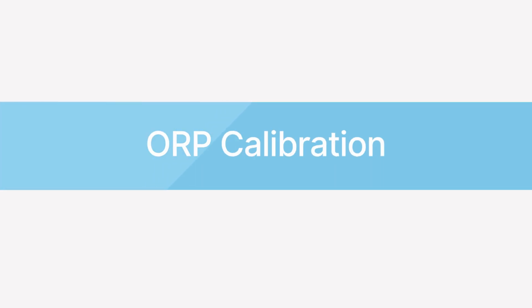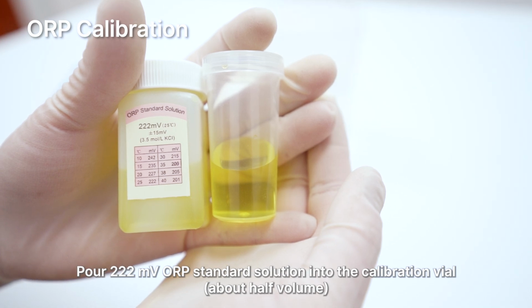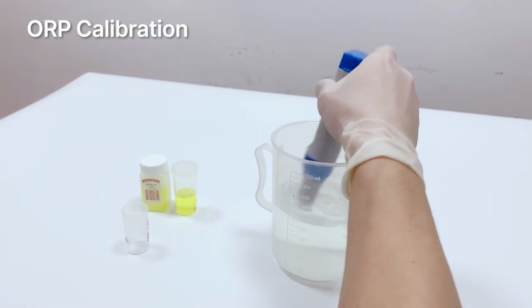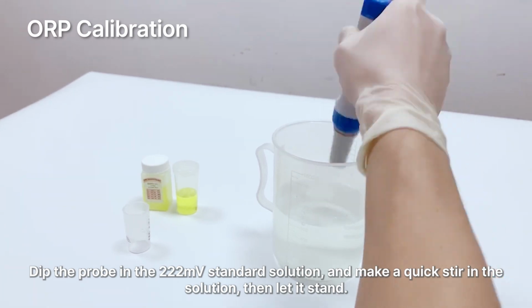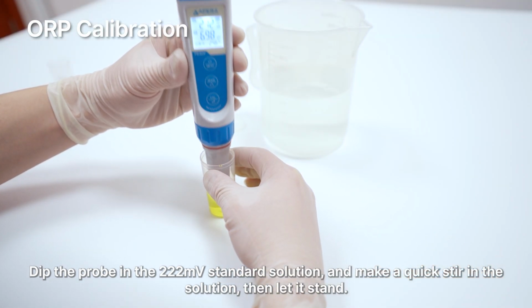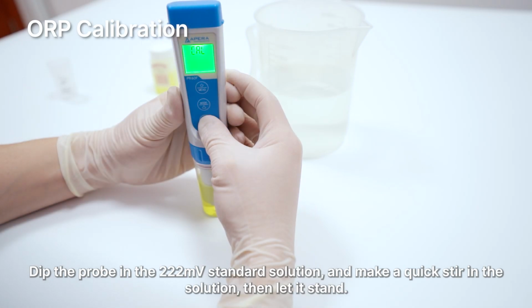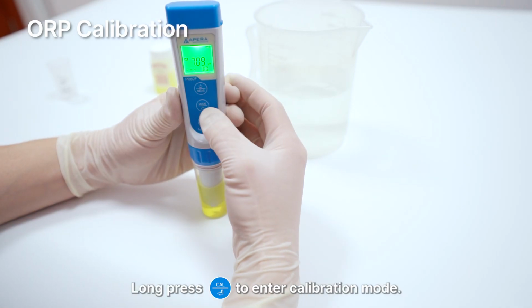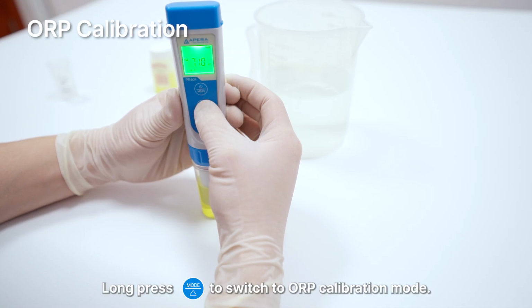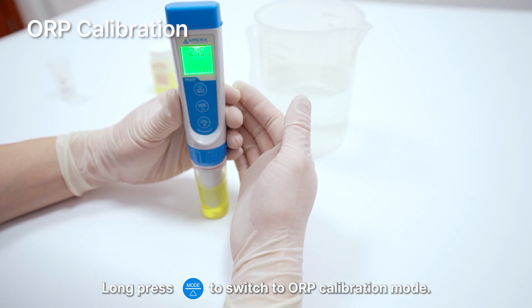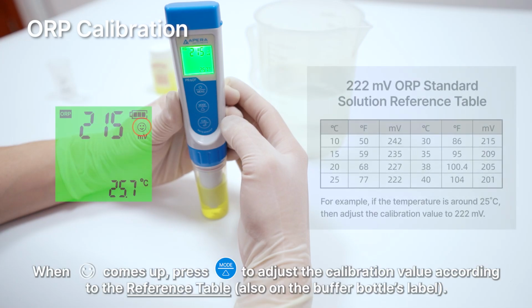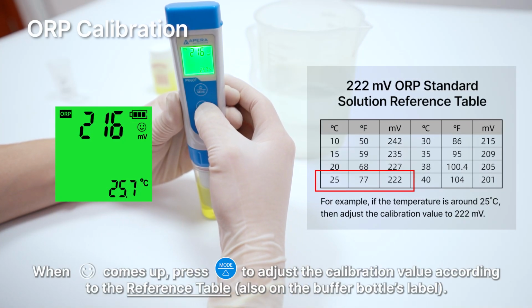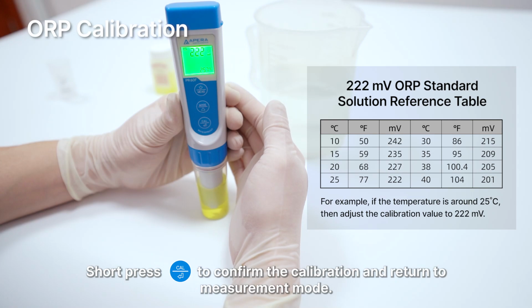ORP calibration. Pour 222 mV ORP standard solution into the calibration vial. Dip the probe in the 222 mV standard solution, and make a quick stir in the solution, then let it stand. Long press Cal button to enter calibration mode. Long press mode button to switch to ORP calibration mode. When the smile face icon comes up, press adjustment buttons to adjust the calibration value according to the reference table. Short press confirm button to confirm the calibration and return to measurement mode.